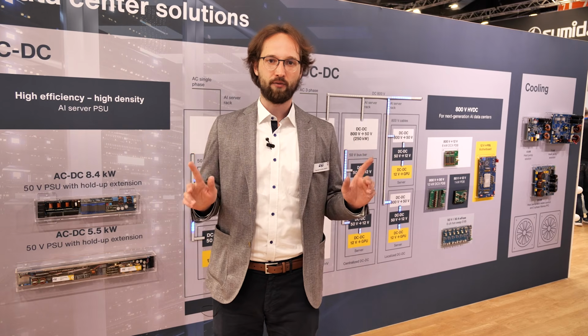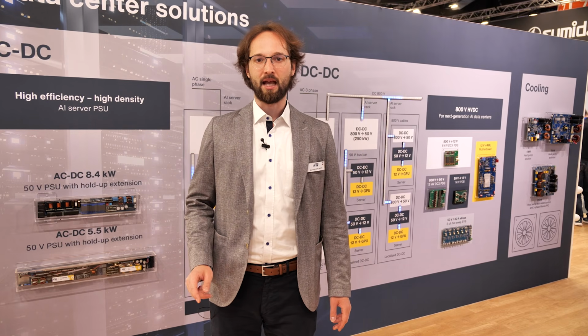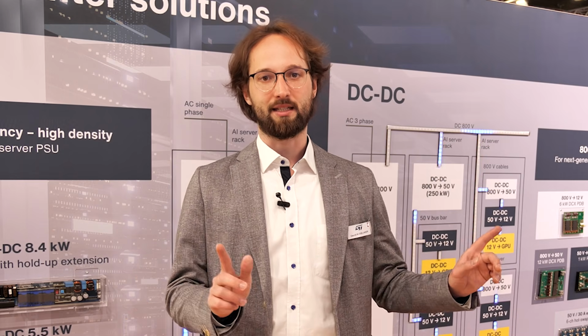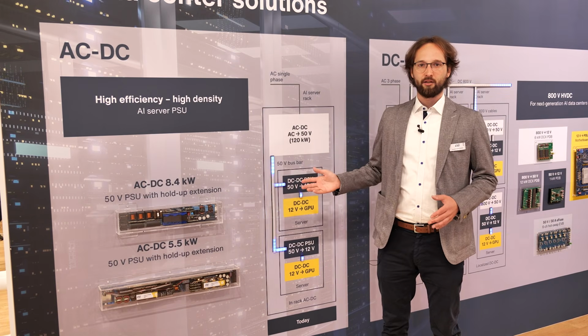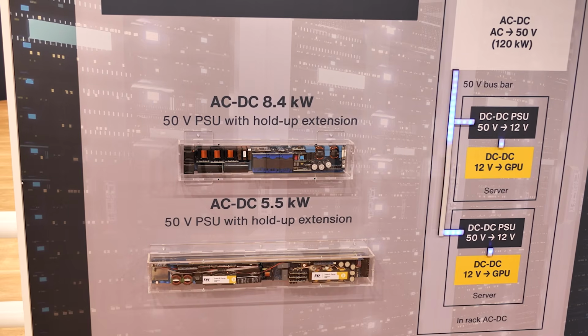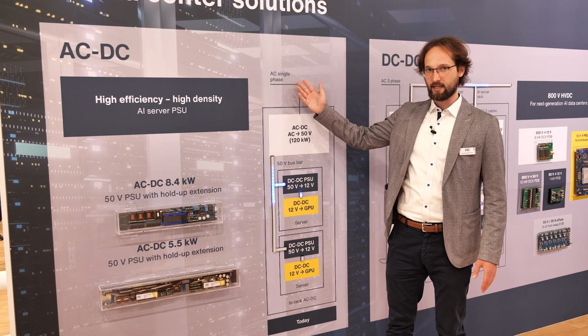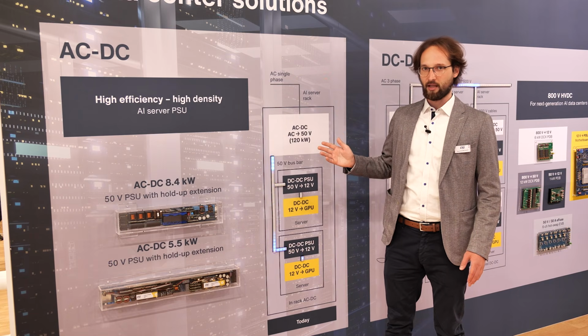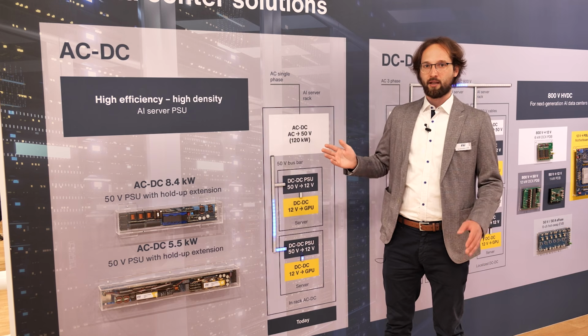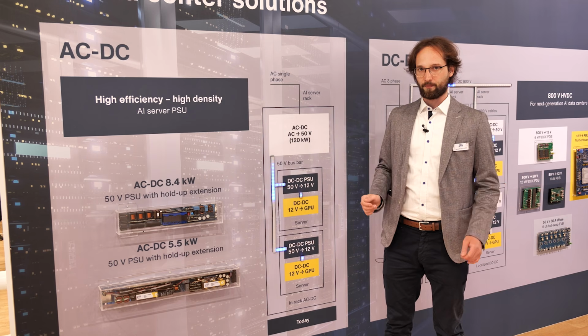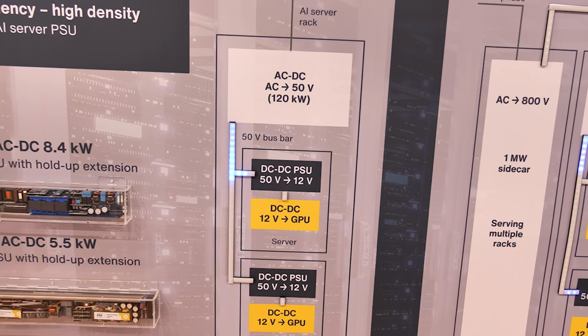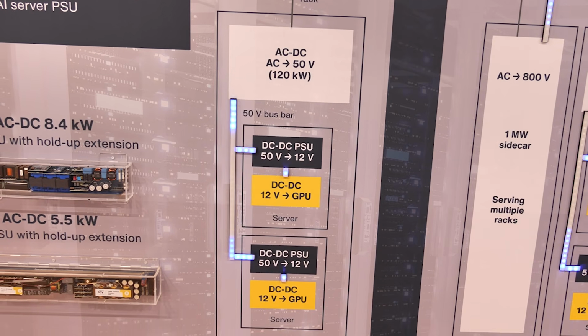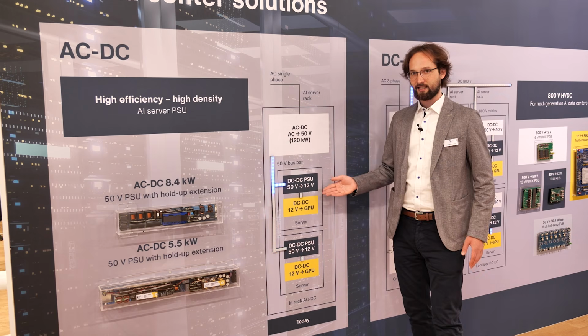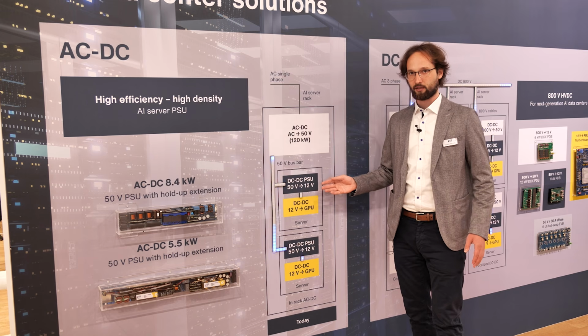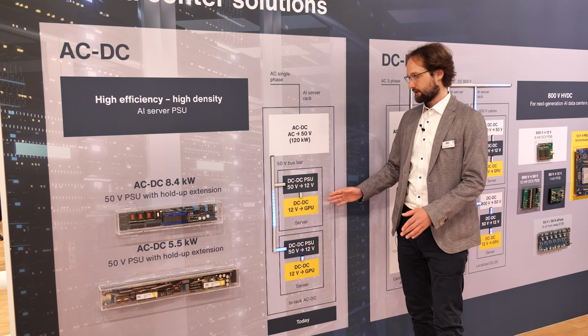All of these solutions are fully in line with ODMs and hyperscaler specs, which is not something many companies in this sector can say. This section shows a conventional server rack. Input single-phase AC is converted at the rack level by an AC-DC stage with a 50-volt output. The 50-volt bus bar distributes the power inside the rack. Each server has a DC-DC step-down stage from 50 volts down to 12 volts, and from 12 volts down to the GPU voltage.